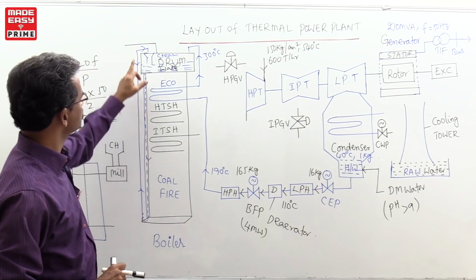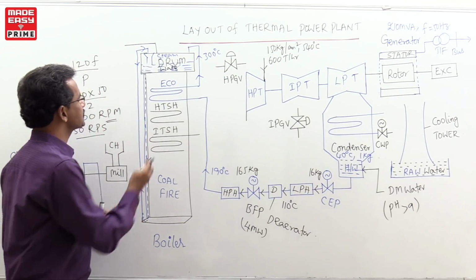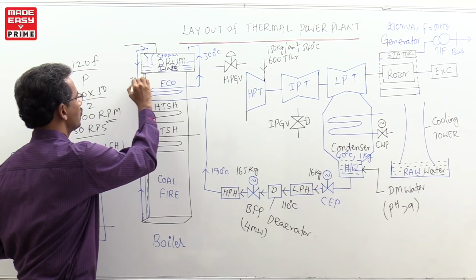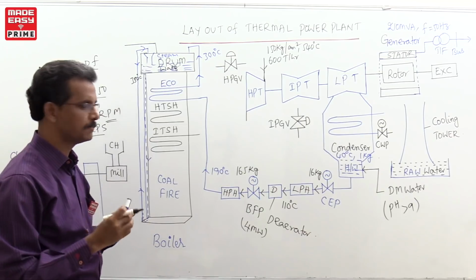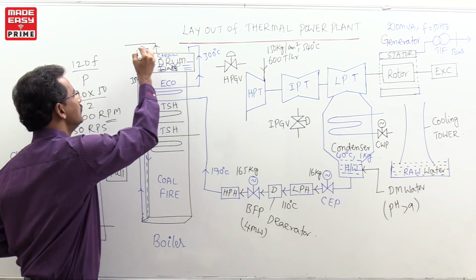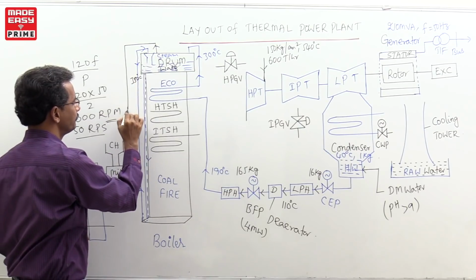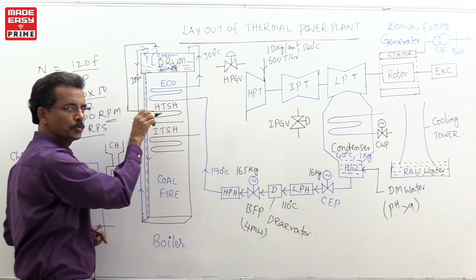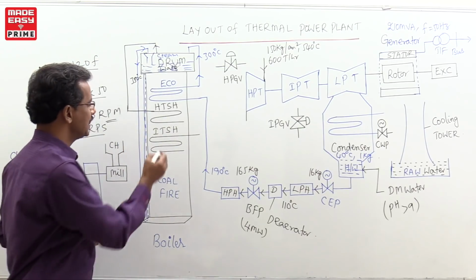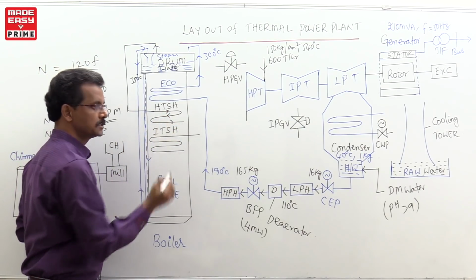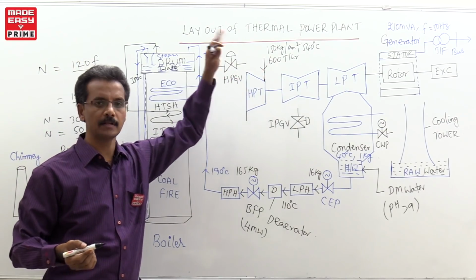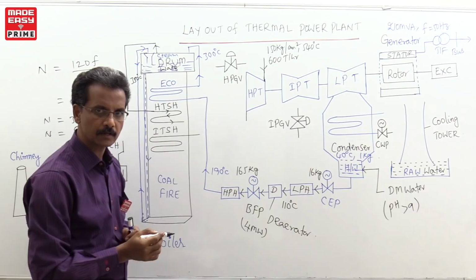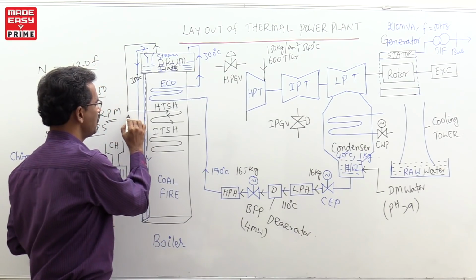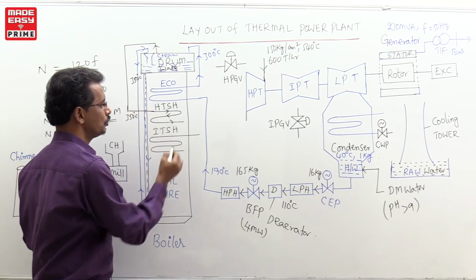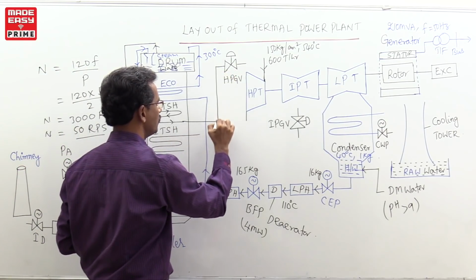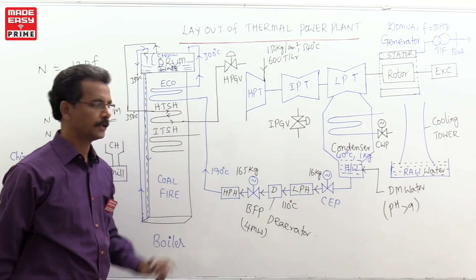Right. Now, as the water and steam enter, the water and steam mixture temperature is raised to around 350 degrees centigrade. Now, the steam which is available is applied to the HT superheater inlet. Here the steam is heated up to the superheated level. It will raise the temperature of the steam from 350 or 400 degrees centigrade to the required value of 540 degrees centigrade.